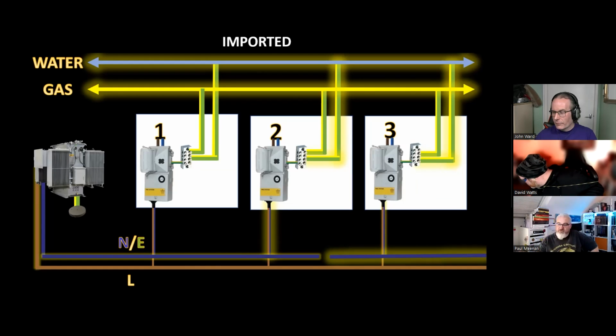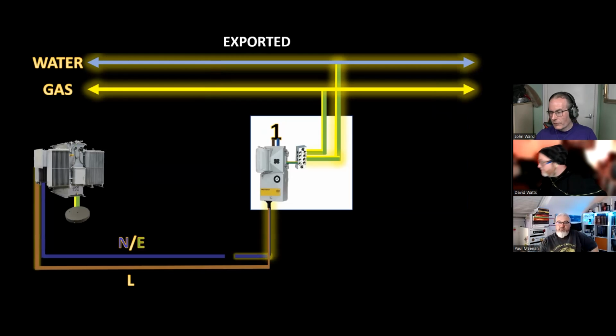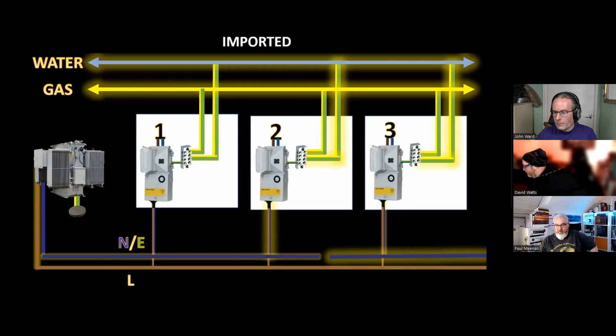So you're exporting your neutral current and importing. I can't read the words at the top because of the way this script is. That's the export one, right? Yeah, I'm getting them the wrong way around, apologies. So that's when you export. When your supply neutral is broken, you export to water and gas. That's when you import, because it's going out and in. But that's just in line with Guidance Note 3 now on how they define it.